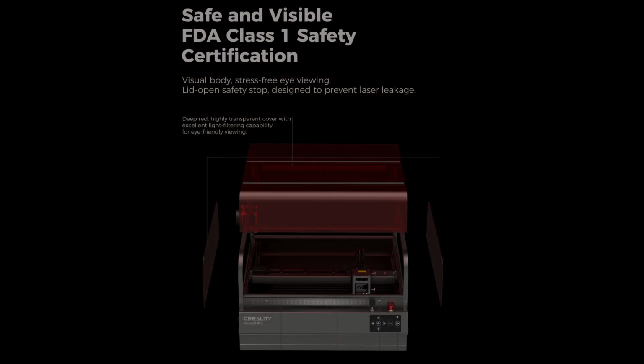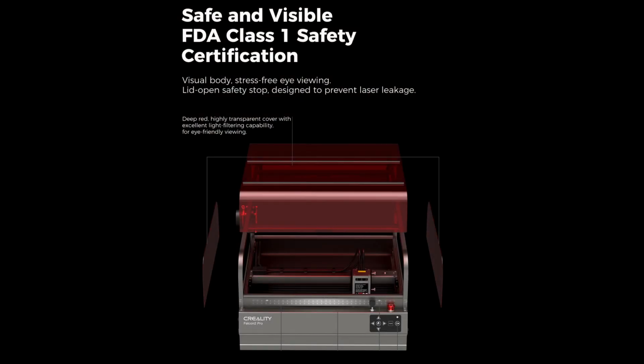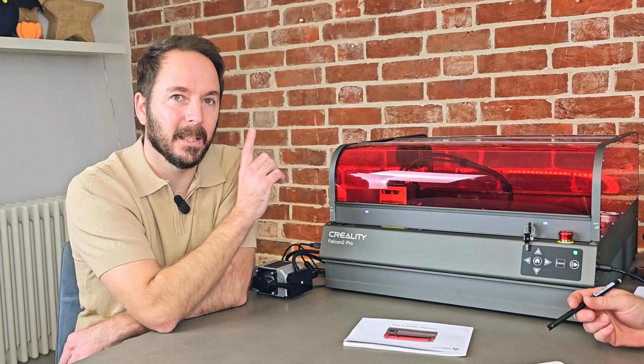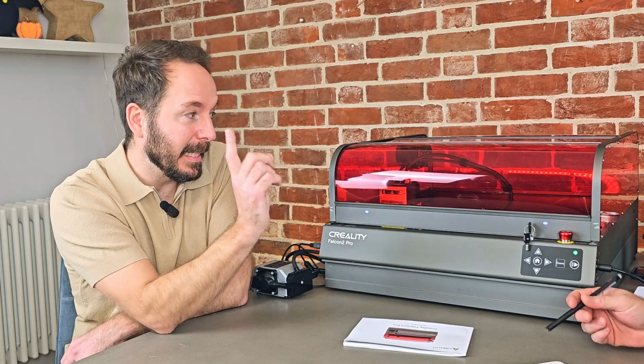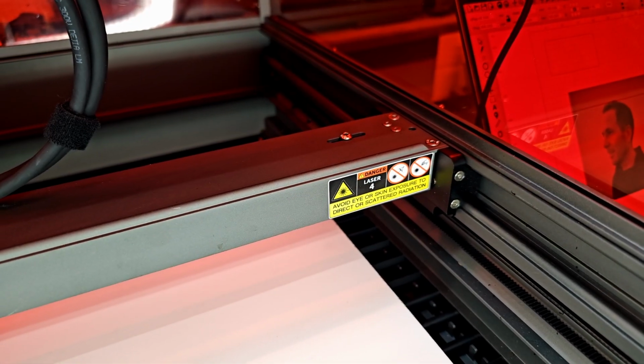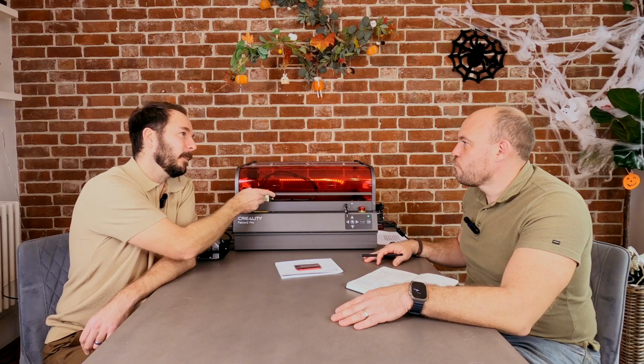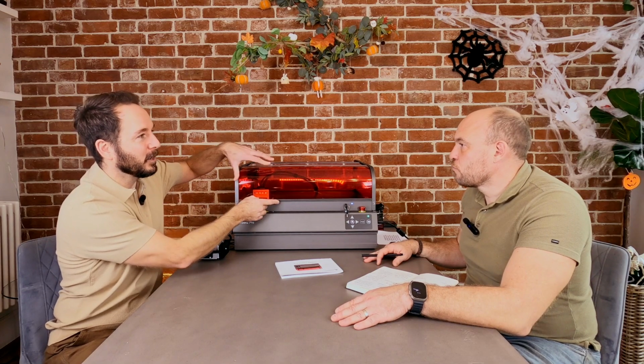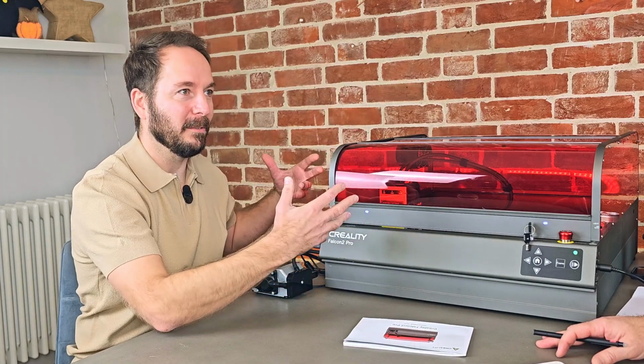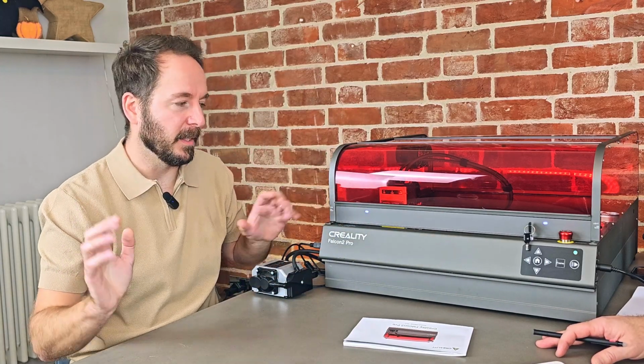So I've seen this classed as a Class 1 laser device. Now, that doesn't mean the laser is safe to look at. I believe it's actually a Class 4 laser with the lid open, but the safety features make it a Class 1 laser when you use all of the safety features and don't bypass them, which obviously you shouldn't do.